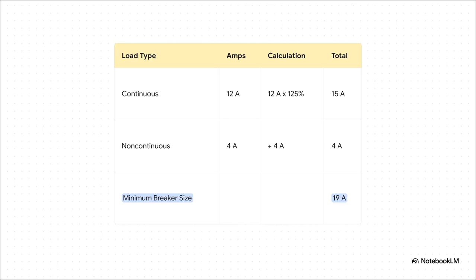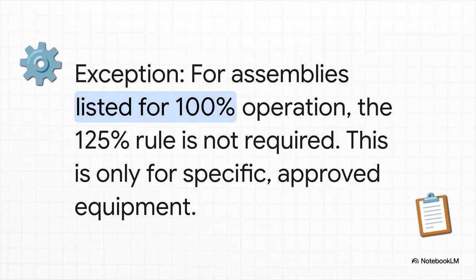It's everything. Now, of course, like any good rulebook, the code does have its exceptions. There are some very specific electrical assemblies and breakers out there that are specially engineered and tested to handle a continuous load at 100% of their rating without overheating. In these specific listed cases, you don't need that 125% rule. But for the vast, vast majority of standard installations, that buffer is absolutely mandatory.